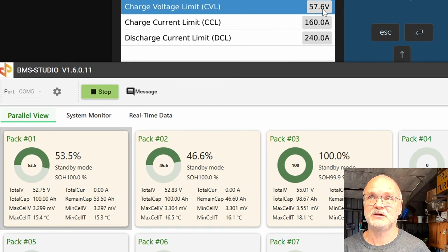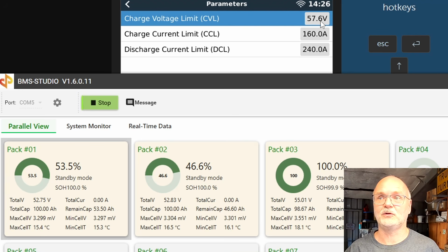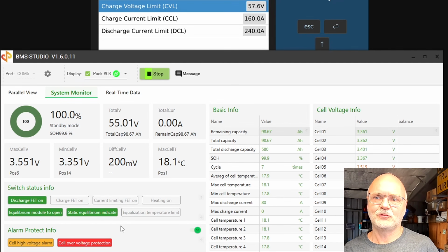It tells the charger to charge to 57.6 volts. But we also know, connecting to the 100% battery, this one cannot be charged anymore because we had a cell over-voltage protection, right? It needs to wait for the recovery voltage, which is around 3.55 to 3.6 volts.